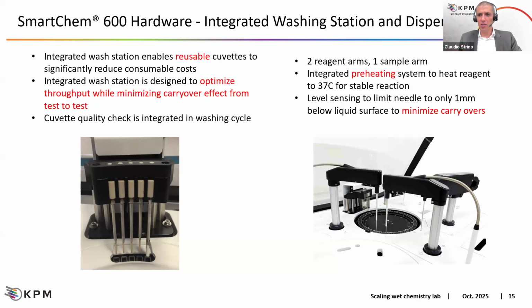And also in this case, we can see that thanks to the level sensing we have on the samples arm and reagents arms, only 1 millimeter of each needle will be in touch with the solutions. So this makes us able to properly clean and wash the needle inside and outside, and to minimize the carryover. So the matrix effect between the different reagents and the different sample matrices.